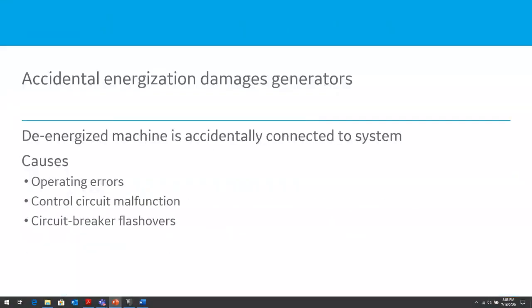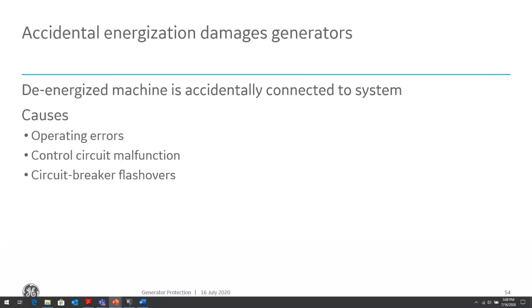Generator accidental energization is one of the abnormal system conditions that we want to protect against. Since this is not a short circuit condition, backup relaying can only detect this condition. So primary relaying would not be able to detect this condition. We're talking about time overcurrent, distance elements, unbalanced protection, reverse power with time delay on it. So they are usually slow, and because the machine was out of service during this accidental energization, those pieces of protection might be out of service for maintenance or testing purposes, because usually when we take an outage, we're in a maintenance period.